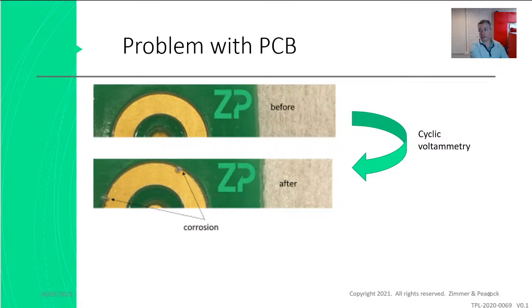We've spent years trying to perfect this. It's very hard to get a good coating of gold over that seed layer. So you apply this voltage, but there are little pinholes in the gold, and the underlying nickel or maybe chromium starts corroding, and you get a massive current. So you know something's instantly wrong.